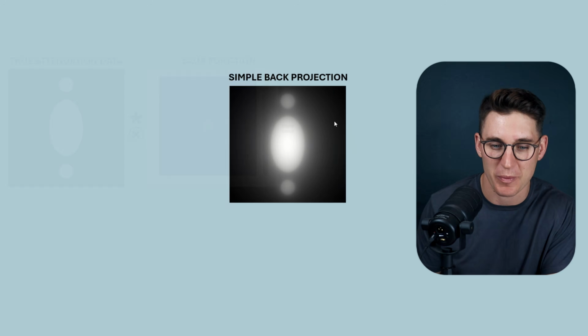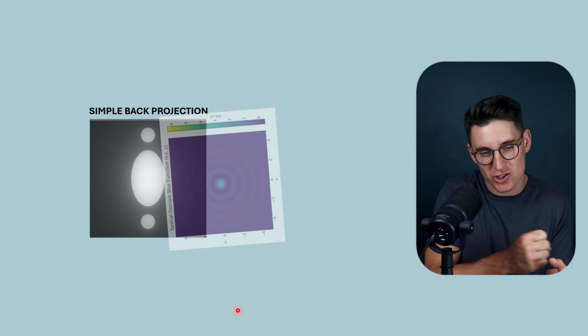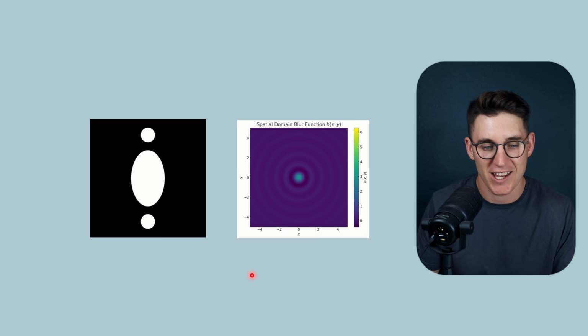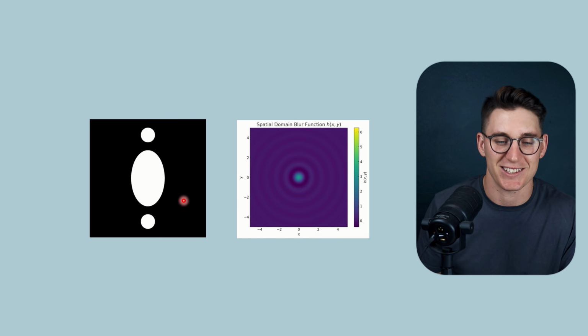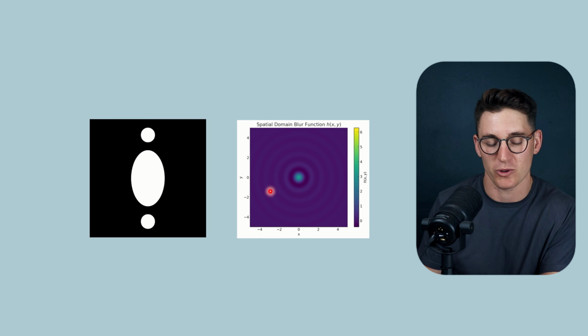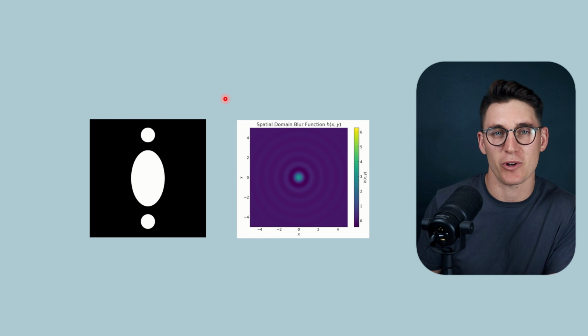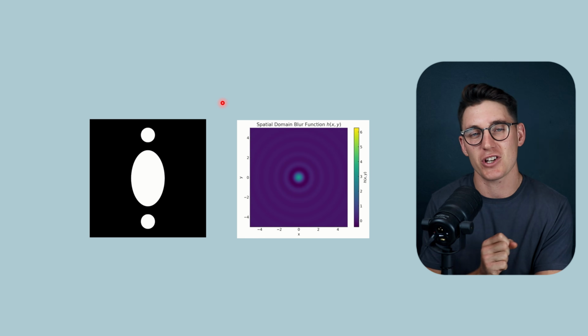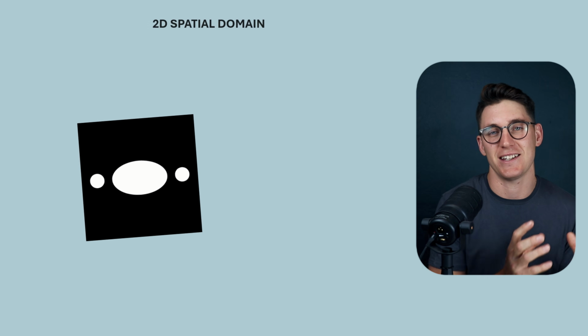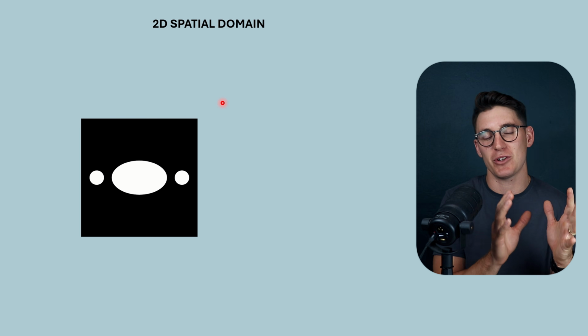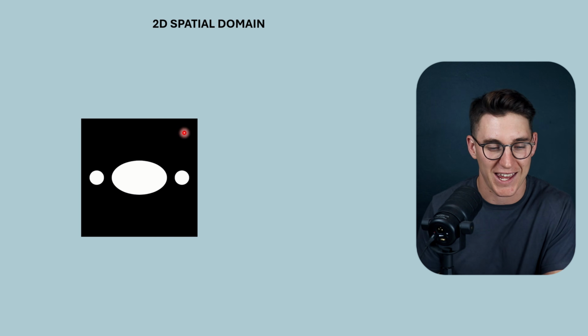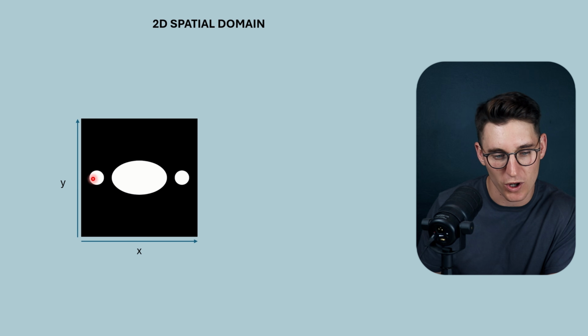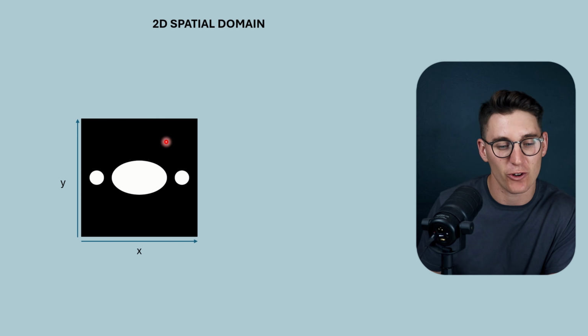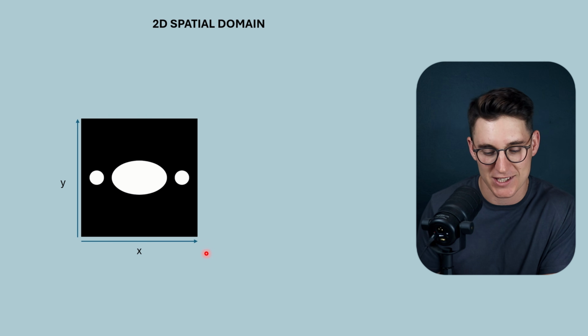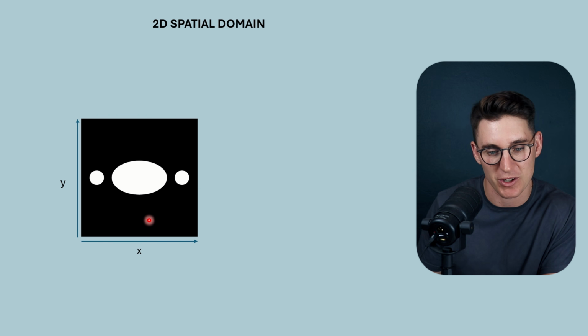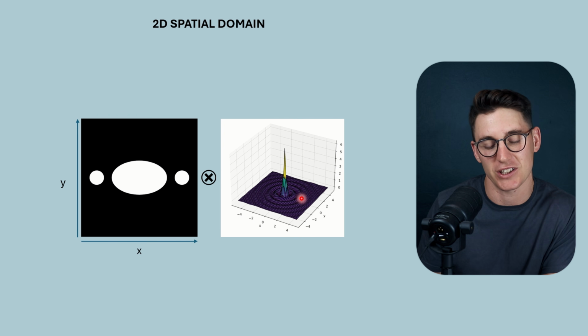So we take our simple back projection image. Now we need a way of extracting that blur function out and calculating the true attenuation data. That's filtered back projection. Let's look at that a little bit more closely. Now, in order to remove this blur function using filtered back projection, we first need to understand how blur is represented in an image. And up until now, we've been looking at images in the 2D spatial domain. We've got X and Y coordinates that show us what the attenuation value is at specific locations in this 2D image. And we said that blur is introduced into this 2D image by convoluting the blur function here.